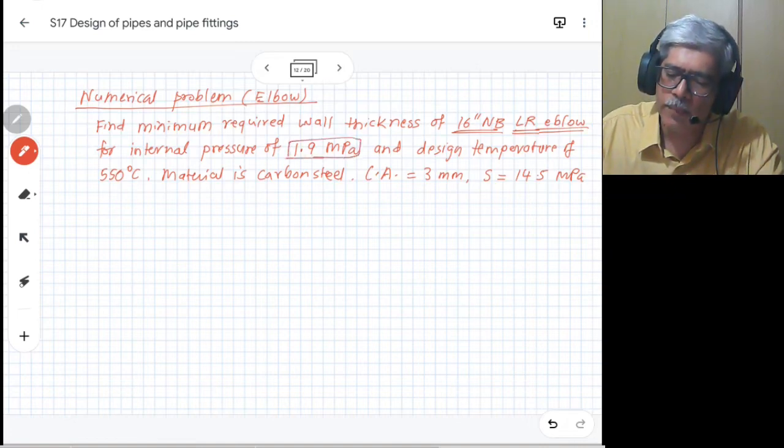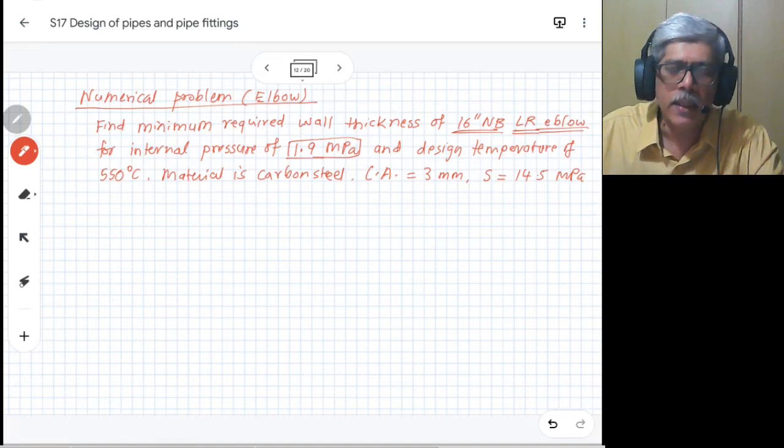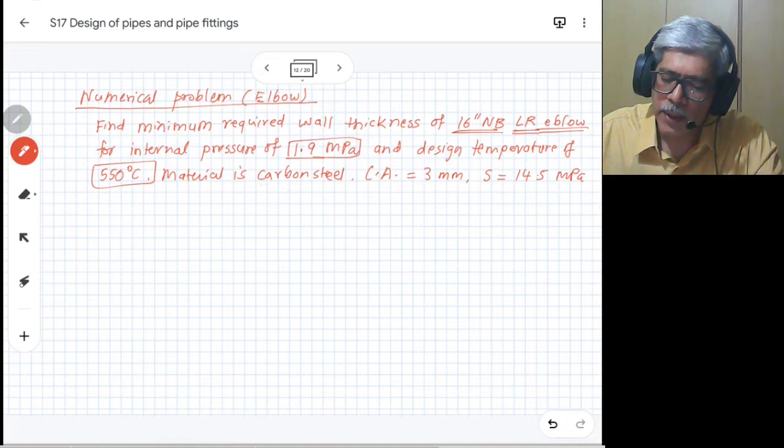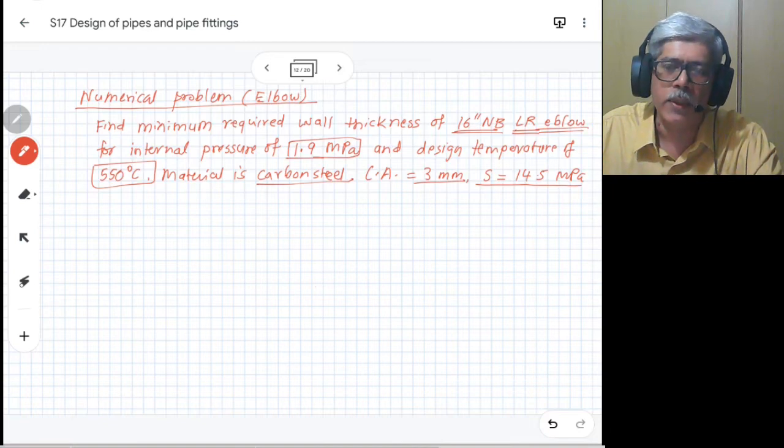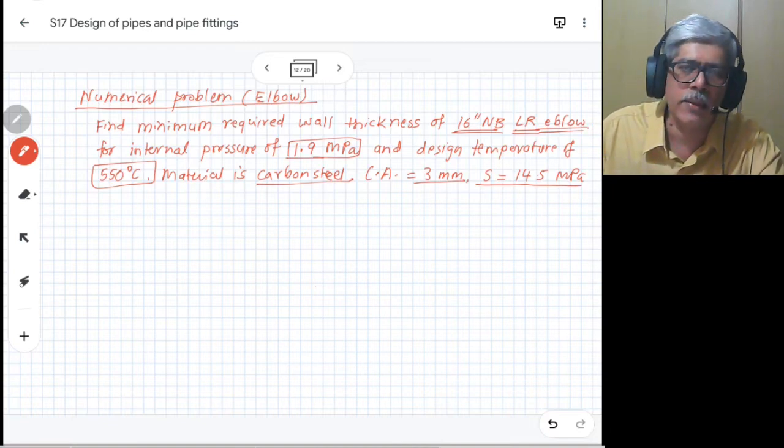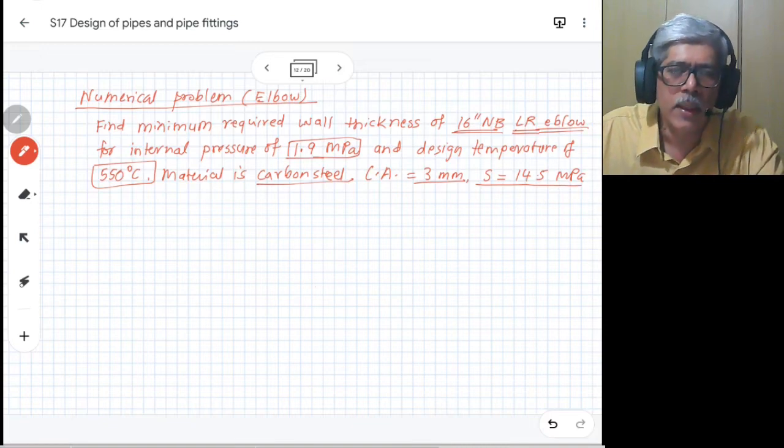For internal pressure of 1.9 MPa and design temperature of 550 degrees centigrade. The material is carbon steel, corrosion allowance is 3 mm, and allowable stress is given as 14.5 MPa. Almost all data except for the design pressure is same as that for the straight pipe which we calculated just a few moments back.